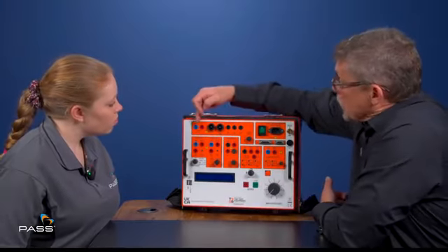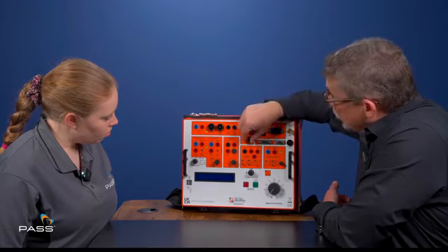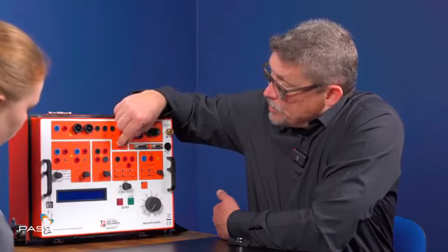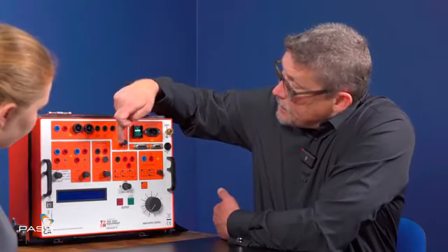The timer, as I'll go through in a bit more in a minute, Jess, is here, but that will give you 1 millisecond resolution, which is more than enough for your average breaker tester. We have a lot of protection. So if we go in here, as I said, we've got the main taps here, but we've also, another way we can control the output is this control here. Now this we can set to 5 through up to 200 amps.